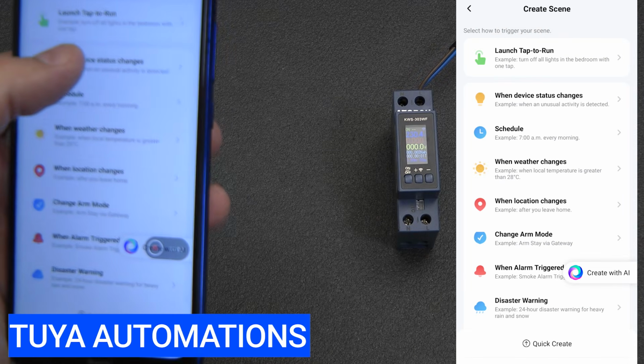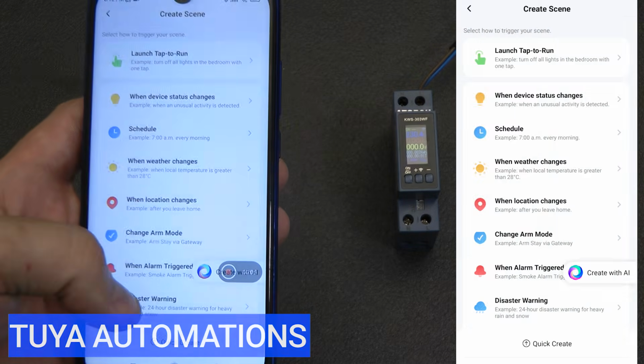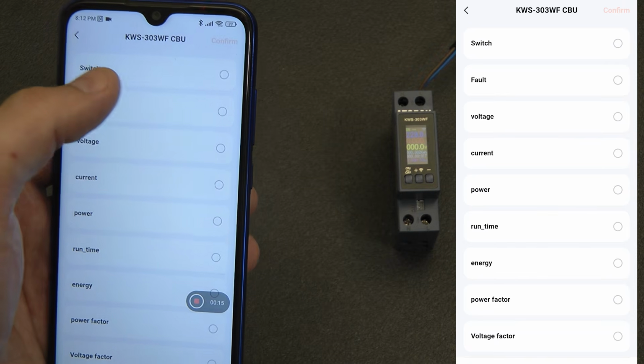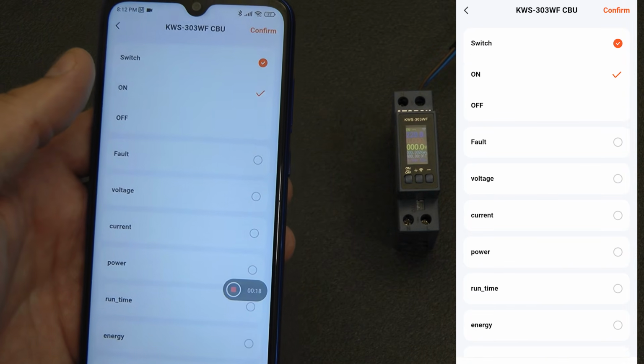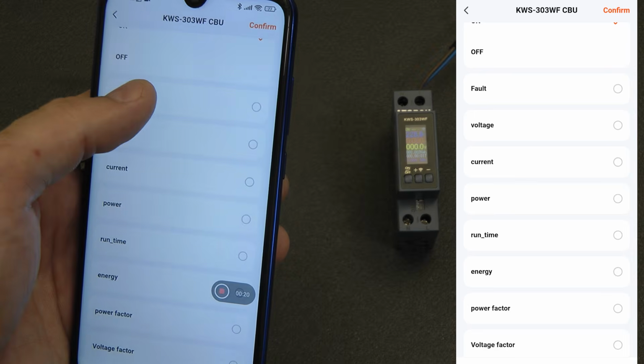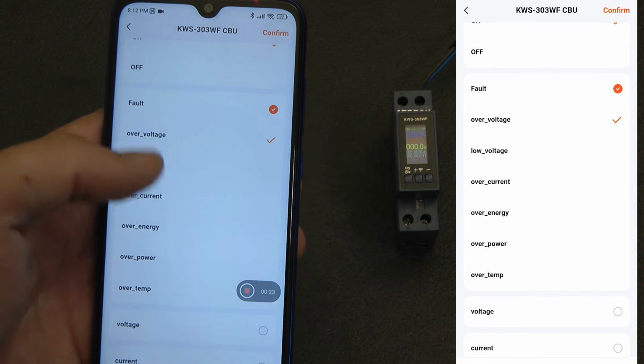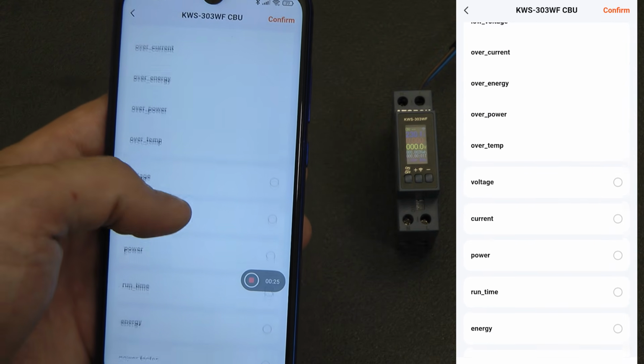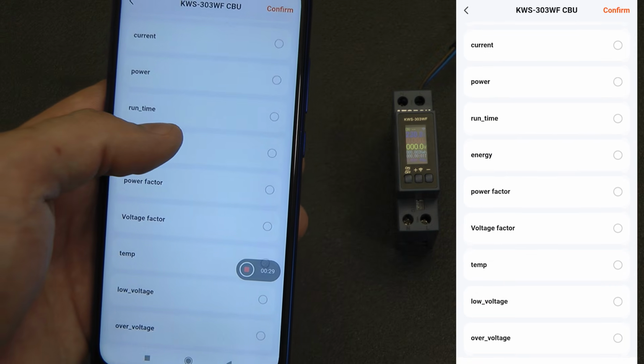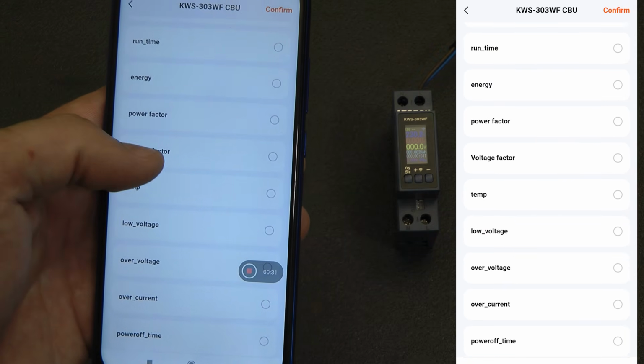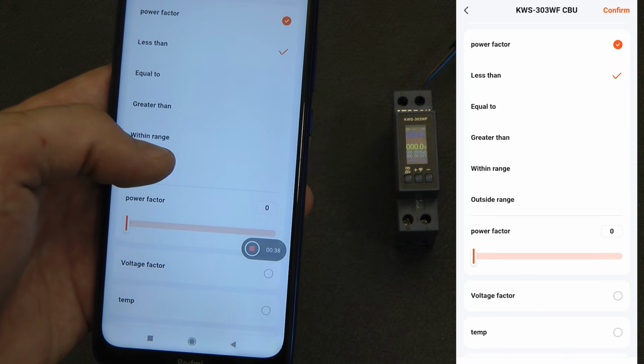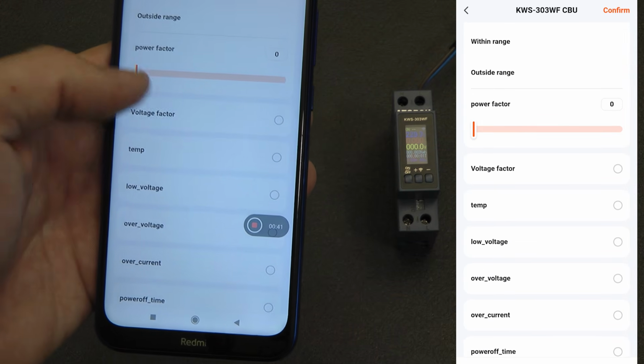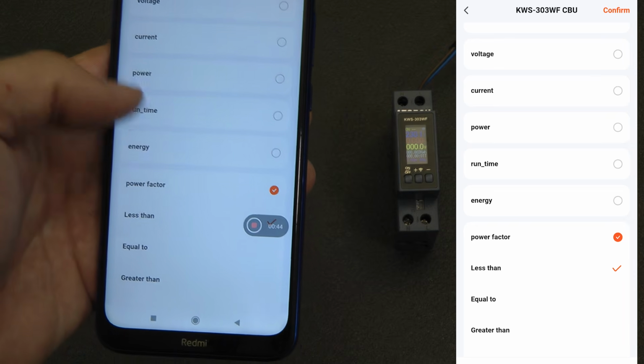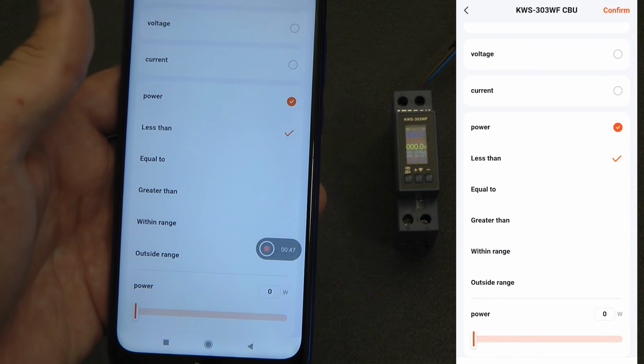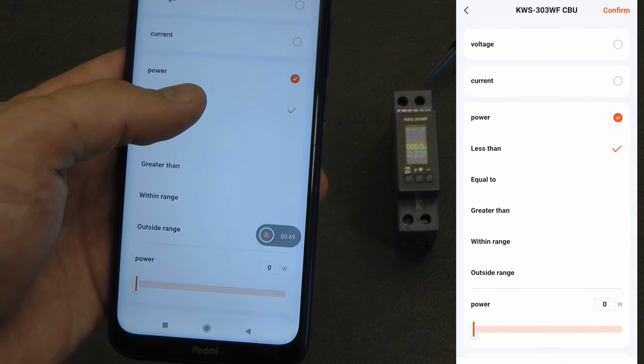Now let's go to the automation section and see what this relay can do as a trigger, meaning in the if condition. There are really many parameters here. The most obvious one is the state of the relay, whether it is on or off. Then there are triggers based on the configured thresholds: voltage, current, power, consumed energy, temperature, and even operating time. The main scenarios, in my opinion, are voltage control and load power control. For example, if there is a strong voltage drop or overvoltage in the network, you can also turn off other devices. Or if the load exceeds the set threshold, then send a notification or launch another scenario.